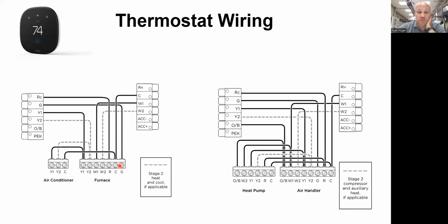So the transformer is usually located in the air handler. The transformer takes the high voltage power, 120 or 240, whatever it is, and drops it down to 24 volts, because almost all thermostats and the control boards they're tied to work on 24 volts. So the furnace typically is the owner of that, or rooftop unit, or air handler, whatever you have. And that guy provides power to other things. Specifically, in this case, he's going to power up this thermostat.